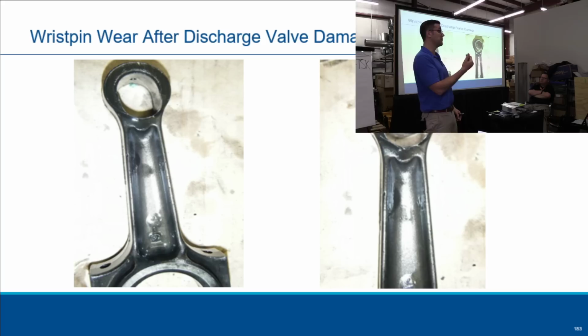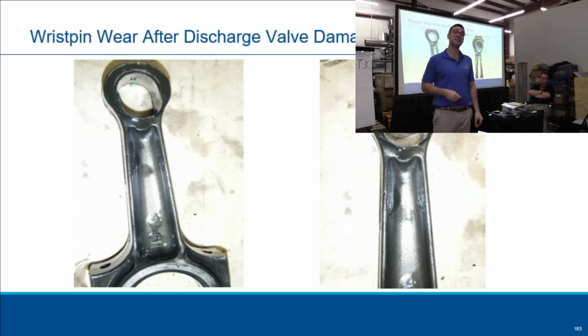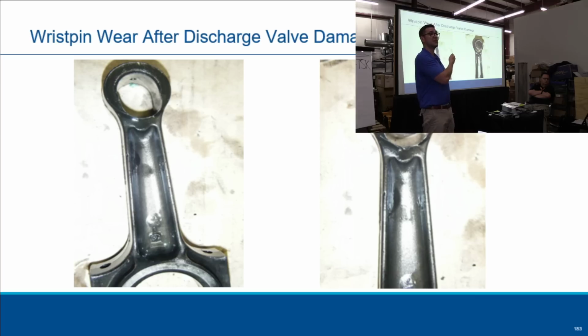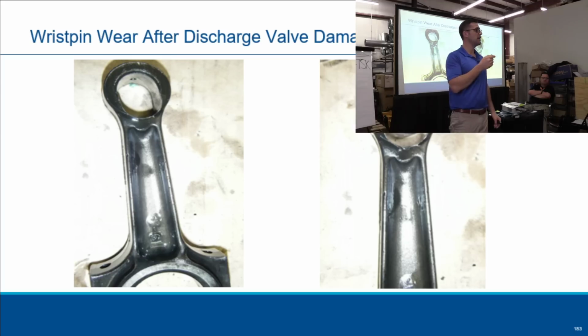And yes, 100% you can replace that valve plate and start it back up. But when you start it back up and you hear this knock, knock, knock, your customer after a week or two is going to say that compressor needs to go. So now you just cost your customer a couple thousand dollars to do a replacement, and now you have to change the whole compressor. If you have wrist pin damage, you have to replace the compressor. How do you think you do a wrist pin test?